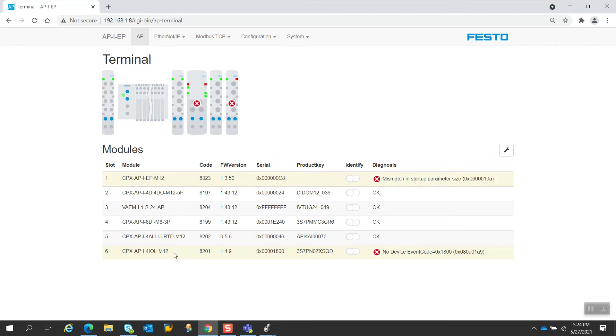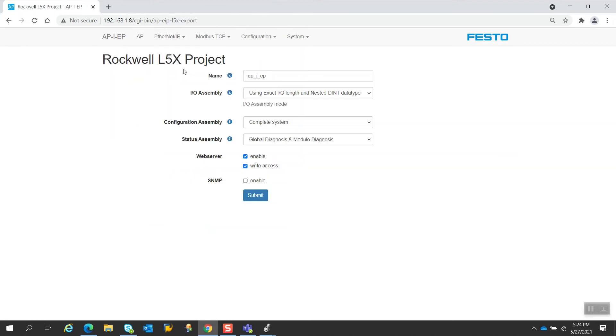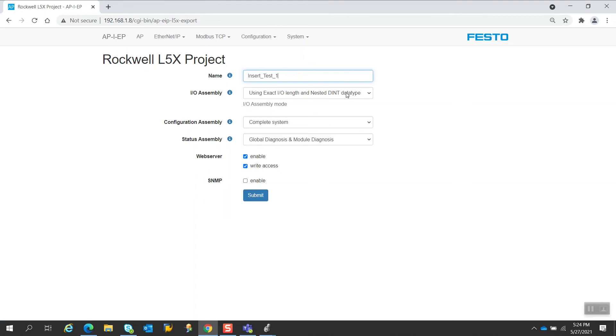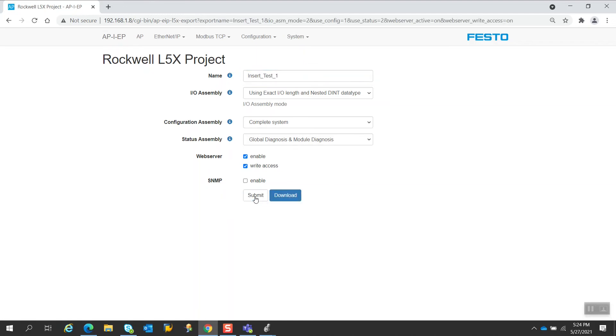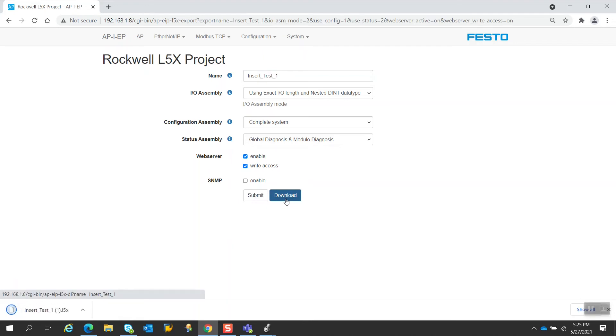So how we're going to do this now, once this is all entered in here with the new module, the user will go to Ethernet IP, export the project again. The most critical step here is that the name is going to be exactly the same as it was before. So in this case here, this shall be insert_test_one, capital I, capital T. Everything else is going to remain the same. You see we have nested data types will be included, and we'll select all the same other values for the configuration assembly and the status assembly.